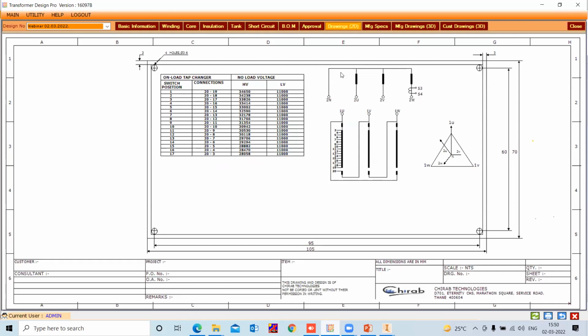Now you can see we have selected OLTC and the tapping range, and this terminal marking plate is generated accordingly. The number of switch positions are 17. The connections are given. Against that connection, the no load voltages and the LV voltages are shown. Then we use the CT for W phase. If you want to use that CT in neutral phase, then that option is also available in the fitting and accessories page. And these diagrams are generated based on tapping and the vector group selection.